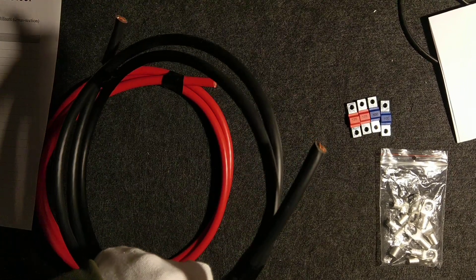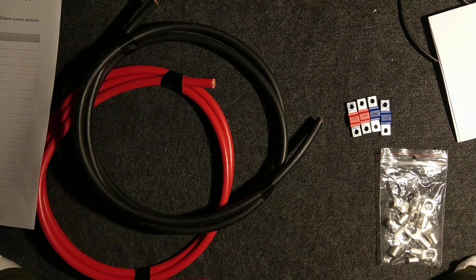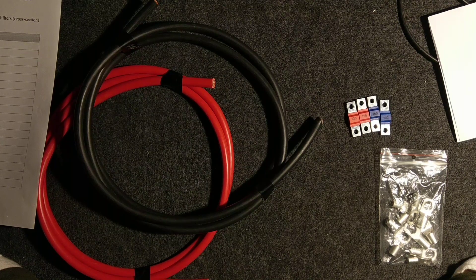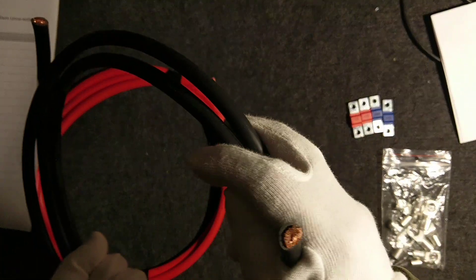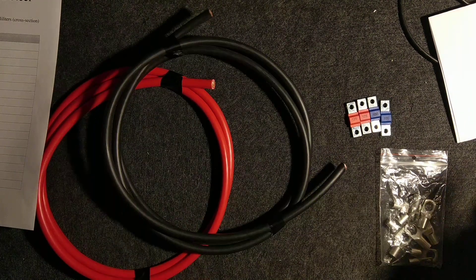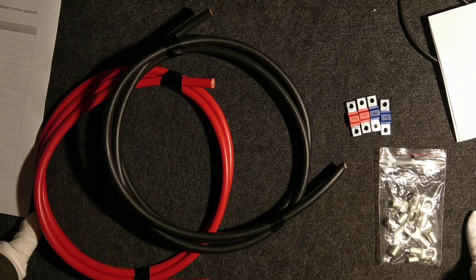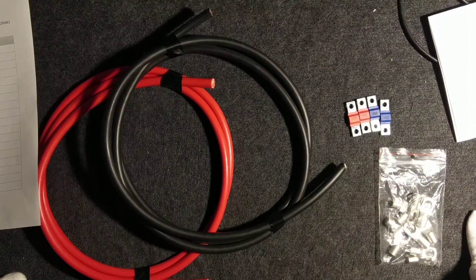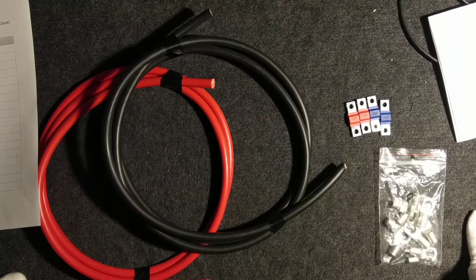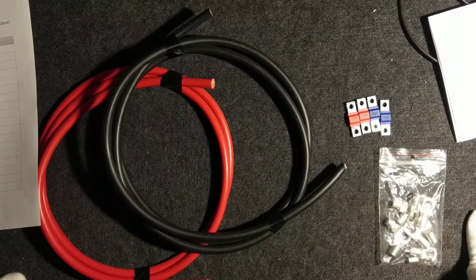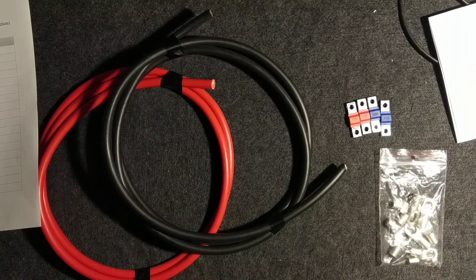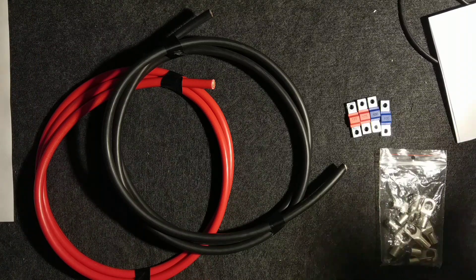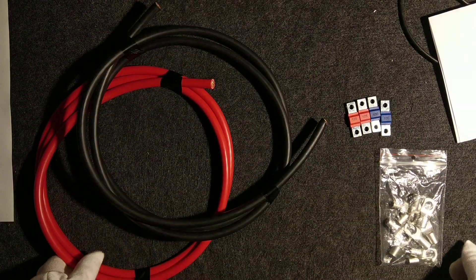Thirty-five square millimeters is the cable that gives you safety, because if you use a very small cable, you will create a lot of heat and you can cause fire. A very thick wire will give you safety and you will not have losses, because if you use smaller cable, for example 16 square millimeters, you probably won't cause fire, but the cable will become hot, and hot means voltage drops. This also means that energy from the battery, instead of going to your household, goes into heat, and you have a heater in your garage or wherever the solar inverter is installed.